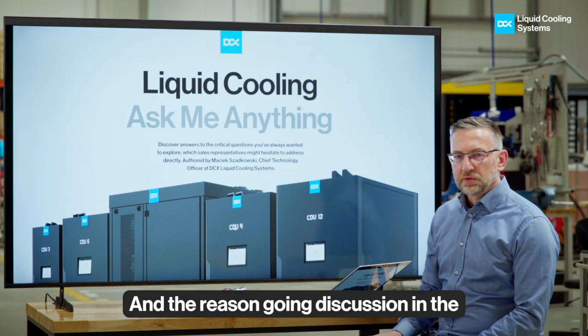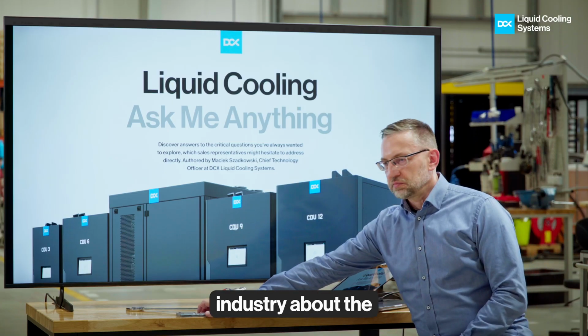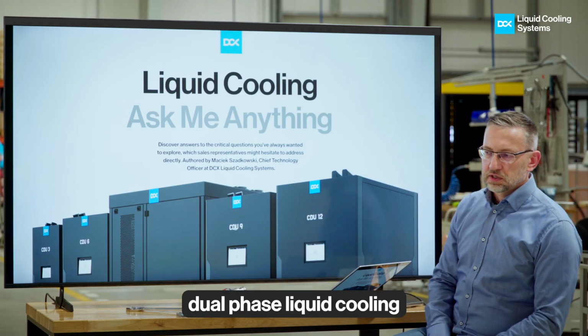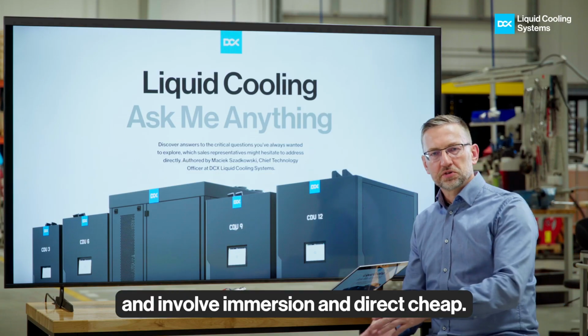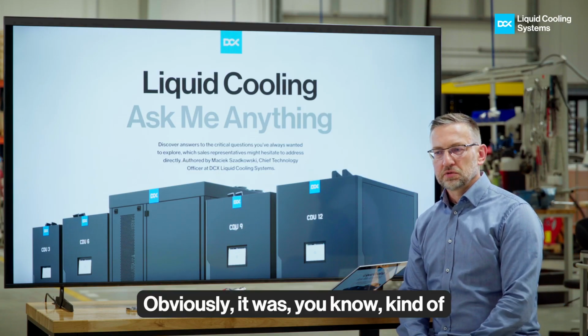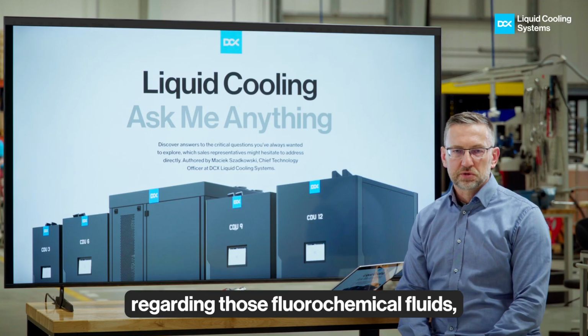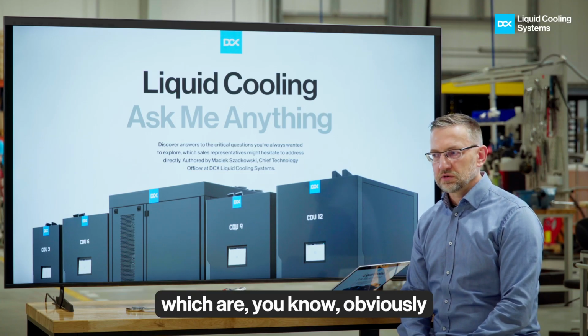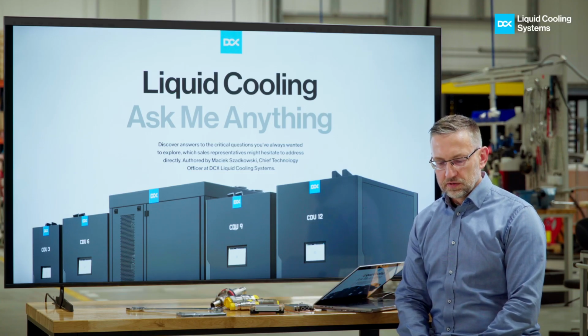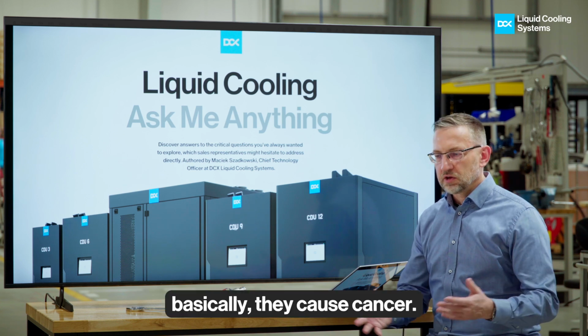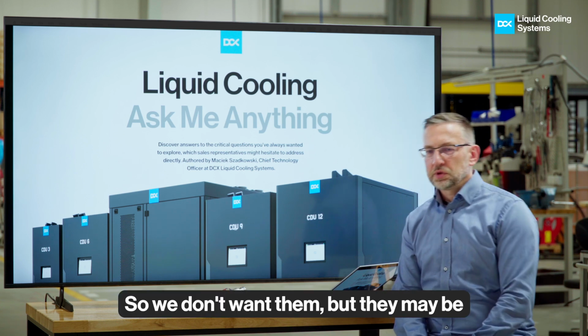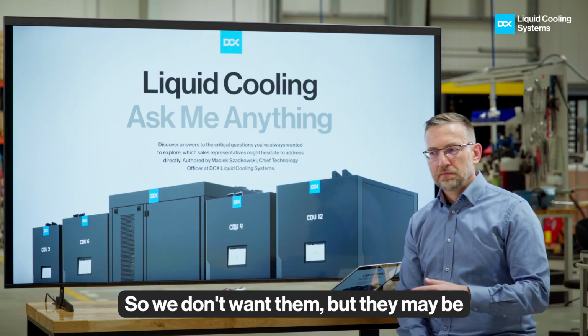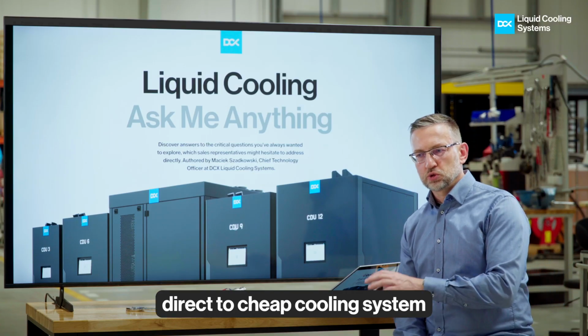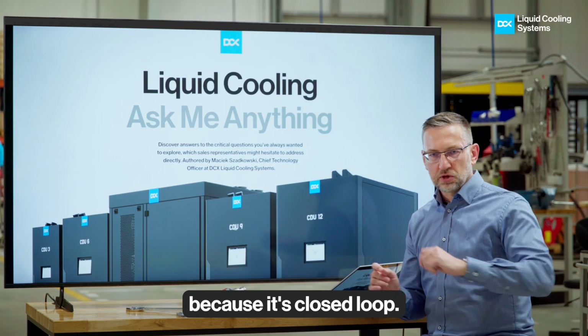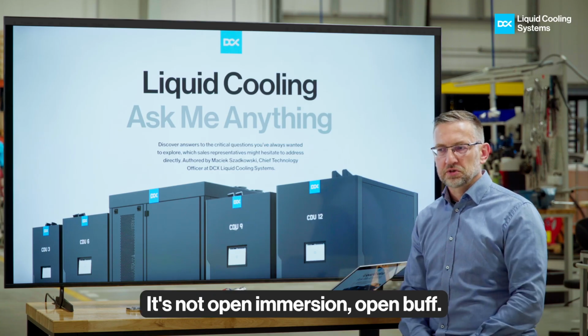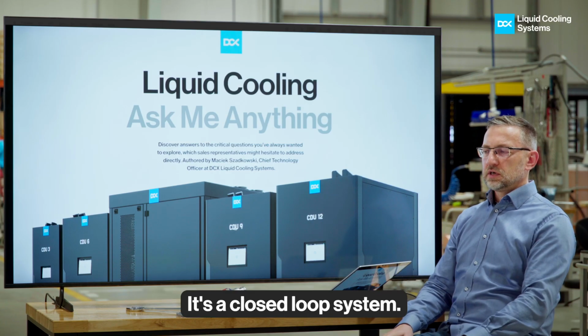There's ongoing discussion in the industry about dual phase liquid cooling, in both immersion and direct to chip. It was kind of suppressed due to problems with fluorochemical fluids, which are unhealthy and can cause cancer. So we don't want them, but they may still be used eventually in direct to chip cooling since that's a closed loop system, not open immersion.